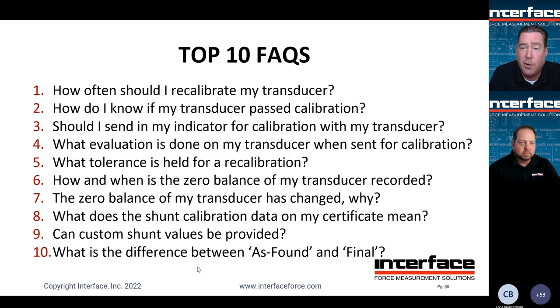If the zero balance of your transducer has changed, why has it changed? There's a couple potential reasons why. The most common one is it's been mechanically yielded, which results in a permanent shift of said zero balance. That zero balance change is merely a symptom, I want to stress, and is most commonly caused by that mechanical damage. But there are potentially other electrical issues that could cause that zero offset, and oftentimes it requires a deeper investigation to dig into the details of why said zero balance shift.